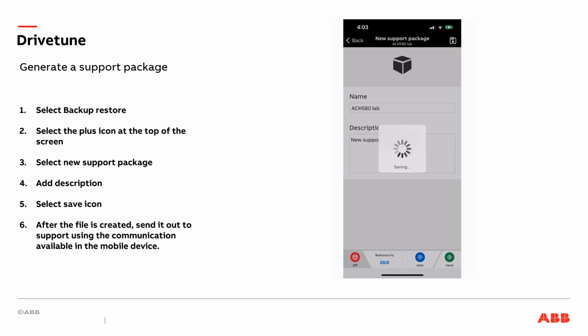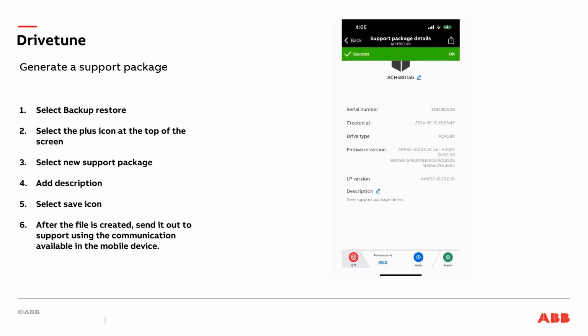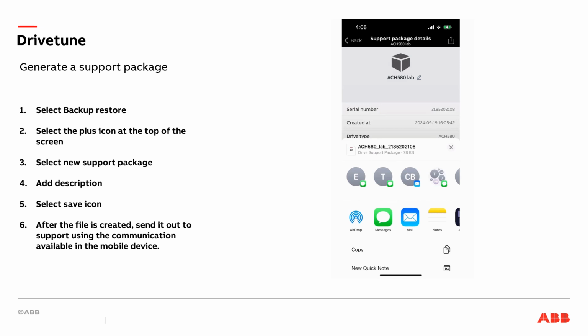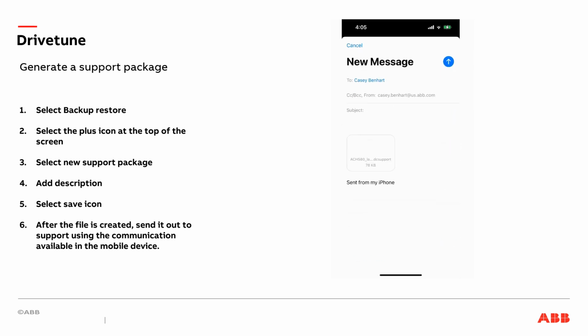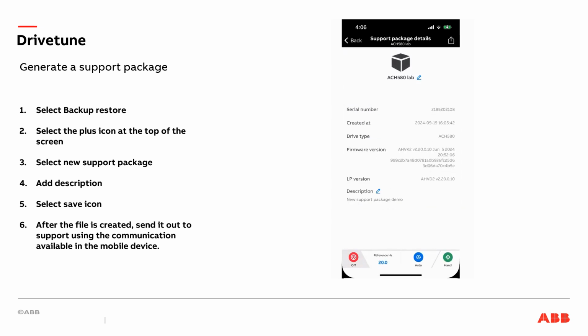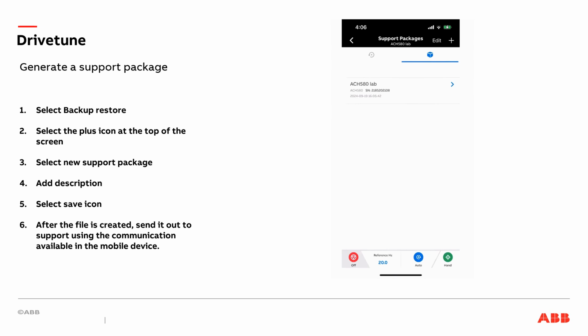This file can be sent to a remote support specialist that can review all the programming in the drive, including the fault history and application-specific programming. When it is completed, you'll get a green OK displayed on the screen. The resulting file can be saved and sent through the mobile device's communication app, such as text or email, for support. The file can then be opened on a PC using a free software called Drive Composer Entry. This allows a full view of all the characteristics of the programming of the drive parameters.